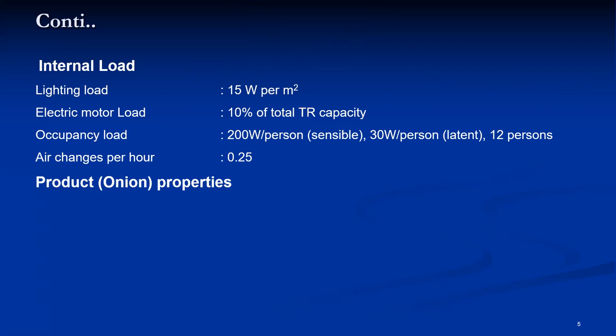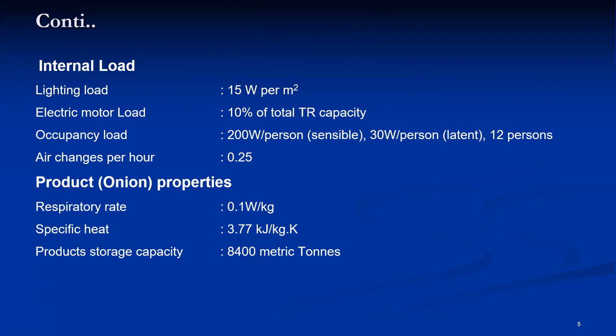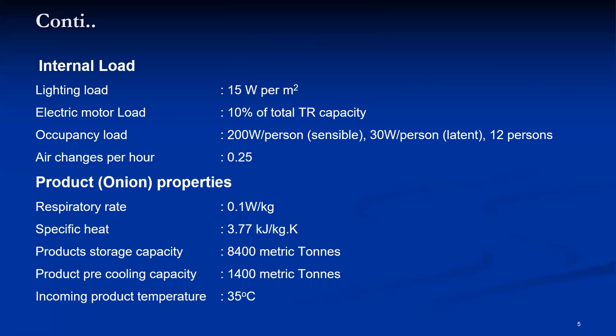The product in this case is onion. The product respiration rate is 0.1 Watt per kg. The specific heat of onion is also given. The storage capacity is 8,400 metric tons of onion. The pre-cooling capacity required is 1,400 metric tons. The incoming product temperature is considered as 35 degrees Celsius, and the cool-down time is 72 hours. This is the basic design data provided, with some data decided by the consultant, some from geographical considerations, and some taken from the design data book.